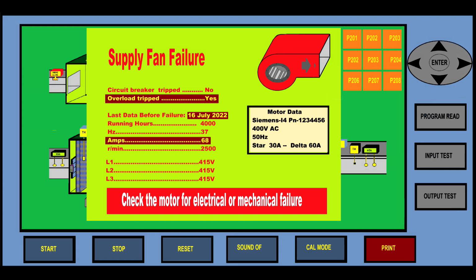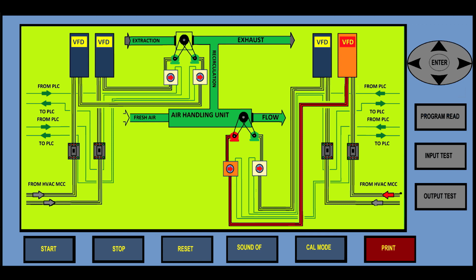Obviously you won't see this inside, that's why we use a PLC and an HMI. The HMI will tell you, for example, supply fan failure, and it will ask you to check the motor for electrical or mechanical failure. It will tell you the rooms covered by this AHU that are being compromised. It will ask you to look at the pressure as well, and finally on the next page it will show you the type of the fault and where to investigate. This drawing will be the real drawing, like on paper, and any modification will be subject to change control. So an electrician will consult this drawing, and the HMI will tell you exactly where to go.